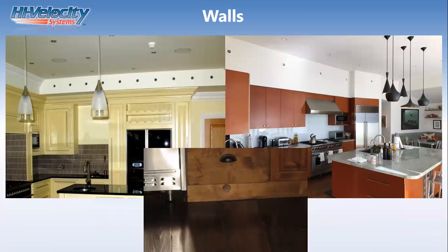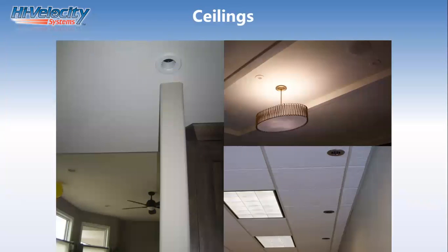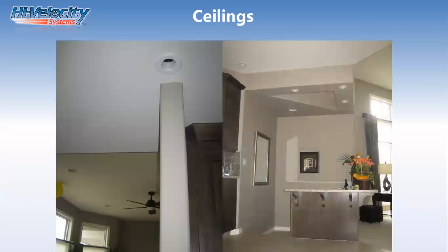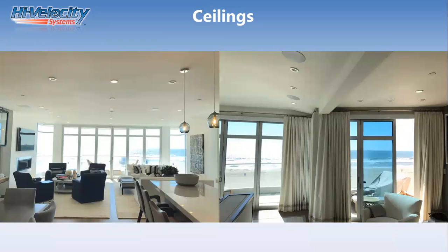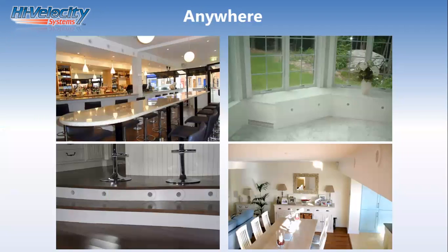In kitchens, underneath in the kick plate was always a traditional location. We always try to look above that kitchen cabinetry where there regularly is some void to locate high sidewall delivery outlets. In ceilings as well, there are times we're going to be installing this stuff in attic spaces or in ceiling spaces, and locating those high velocity ducts symmetrically with the pot lights in the structure to try to maintain good cosmetics within these high-end architectural developments that we often are a part of because of our small duct solution. Ultimately, anywhere you locate these outlets, you're going to get the proper mixing and moving of the room air that you require.